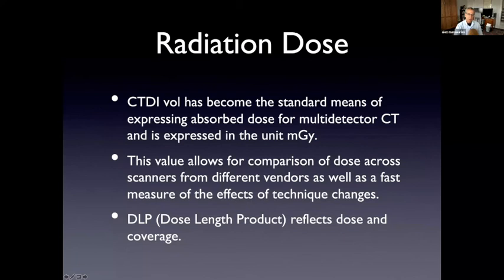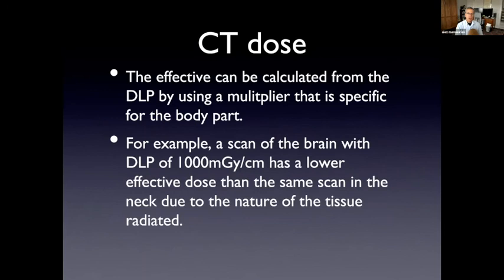The DLP is reflection of the dose, which we get from the CTDI volume and the coverage. So the DLP is going to be larger for, let's say a CTA that covers the head and neck, then it's going to be for a head scan. So the CT dose, these effective doses calculated by using a multiplier that's specific. So for a scan of the brain with the DLP of a thousand, which is pretty standard for a head CT scan, this has a lower effective dose than the same scan in the neck. And this has to do with the tissue radiated. So the effective dose is a calculation based on the applied radiation, but it will vary for the body part.